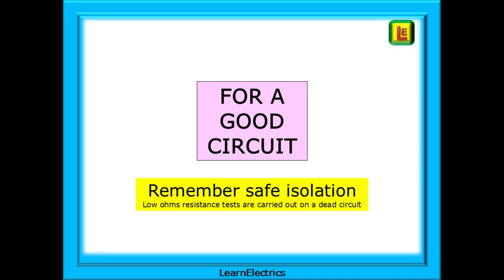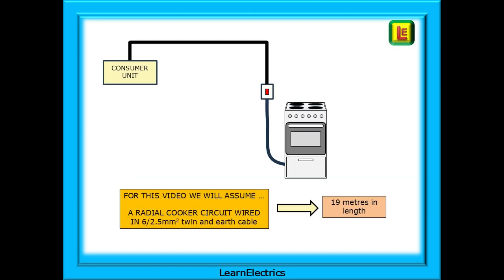Let's start with looking at low ohms resistance measurements in a good circuit — a healthy circuit. What sort of readings should we expect and how do we know if they are correct? For this video we will assume a radial cooker circuit wired in 6 square millimetre by 2.5 square millimetre twin and earth cable, and that the circuit length is about 19 metres in one direction.